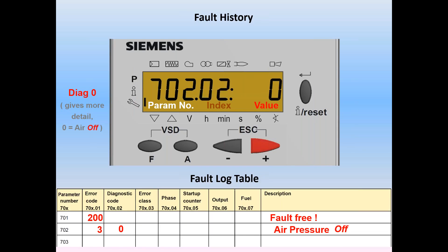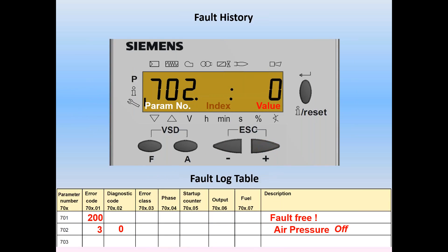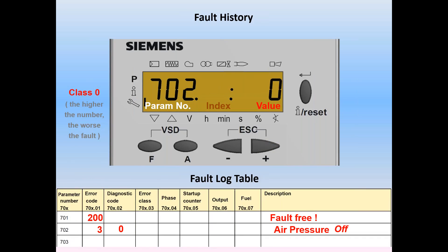We do a plus and since the index field is flashing, we move to index number 3. In this case the index value is 0 — class 0. The higher the number, the worse the fault; in this case it happens to be a lower level fault — it was a purge fault. If you had an air pressure fault during run, it would be a higher class, meaning a more severe error. We log class 0 into the chart at row 2, column 03.